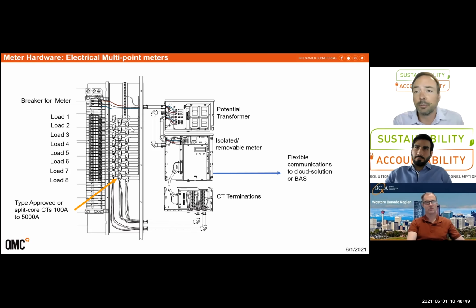And at the same time you're metering plug loads, you're also able to monitor other loads within that distribution panel. So obviously, it depends on how the electrical panel is laid out. If there's a circuit that feeds plugs and lights and a bunch of general stuff, then obviously it's not going to be plug load, but. Correct. And there are a few tricks you can utilize with this kind of technology. You can also use one set of CTs to monitor the entire panel. And then let's say you meter a few lighting loads and a few HVAC loads.